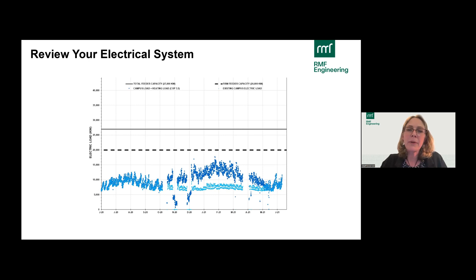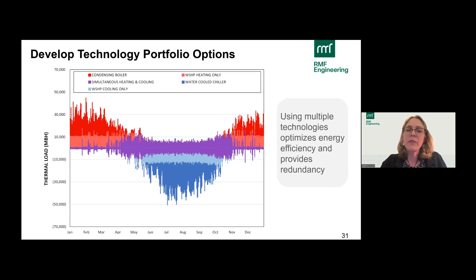The heat pump approach is more like this: the peaks in the winter, when they're heating with electric equipment, are closer to the summer peaks and also below capacity. So they can manage a heat pump project without having to significantly upgrade or increase their electrical capacity. And in the end, many technologies can be layered in to provide the heating and cooling load profiles they need.